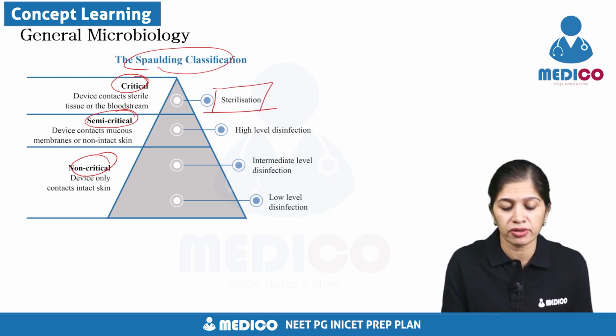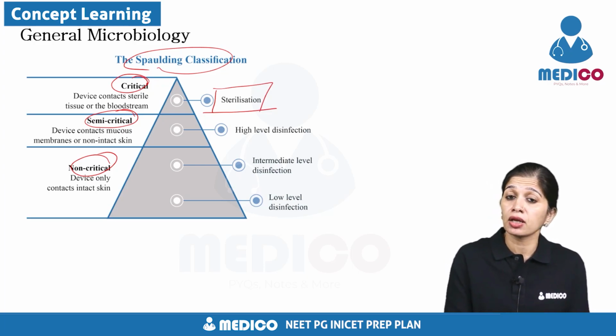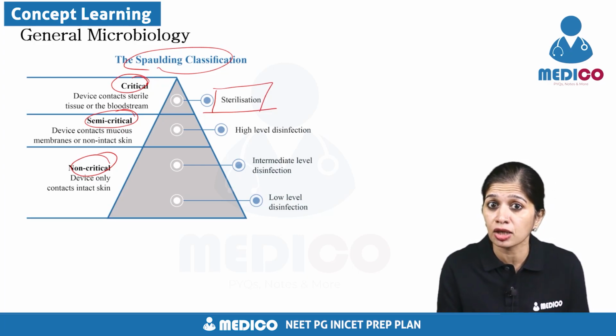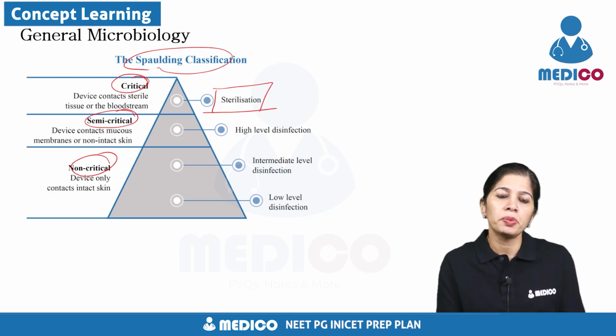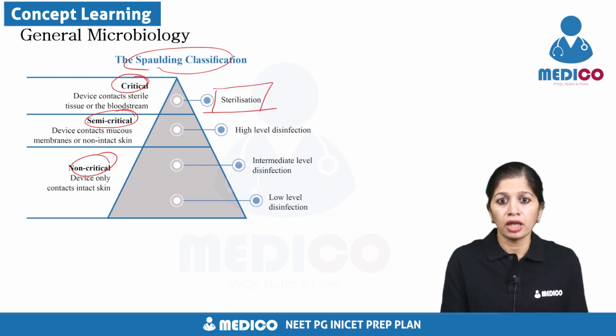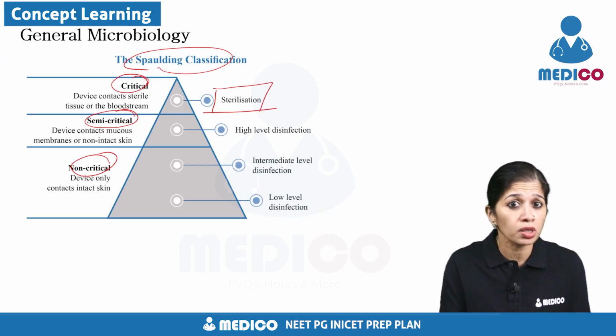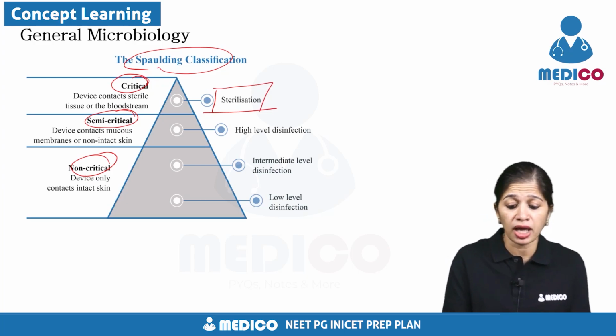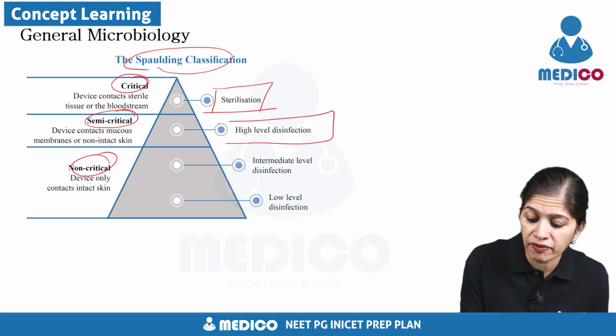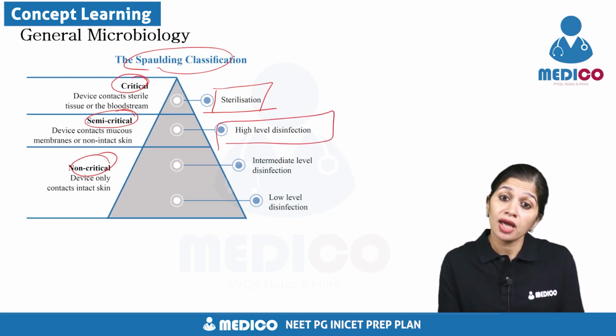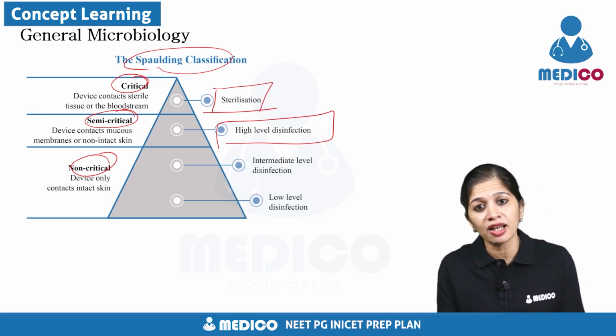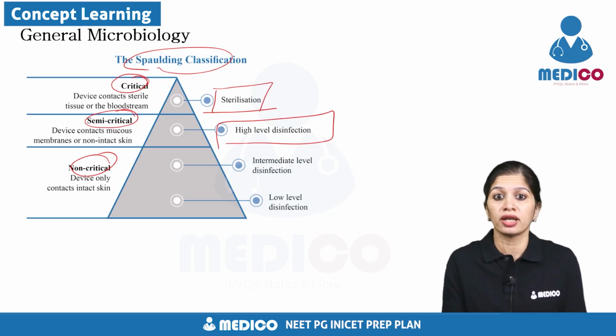What is a semi-critical item? A device coming in contact with non-intact skin or mucous membrane. Example is a scope, an endoscope. It is coming in contact with the mucous membrane. So that requires high-level disinfection. You can sterilize it, but high-level disinfection is still good enough.